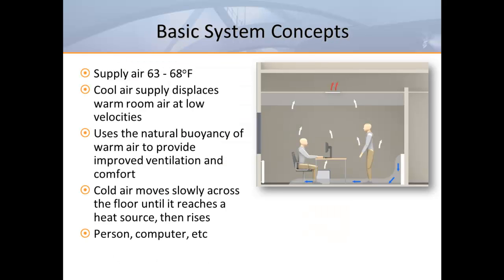Displacement systems typically supply 63 to 68-degree air through specially designed diffusers located on low sidewalls. This cool air discharges at less than 80 feet per minute from the face of the diffuser and quickly cascades down to the floor. The air continues to move slowly across the room in a layer about four inches deep until it locates a source of heat or an obstruction. In office applications, the heat sources in the occupied zone are usually people and equipment. When the slow-moving pool of air encounters a heat load, it quickly rises and carries the heat and pollutants towards the ceiling. Internal heat loads and contaminants are then carried away by the return air — we refer to this as a thermal plume.